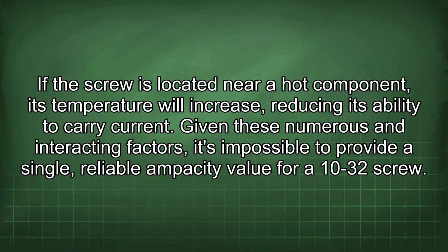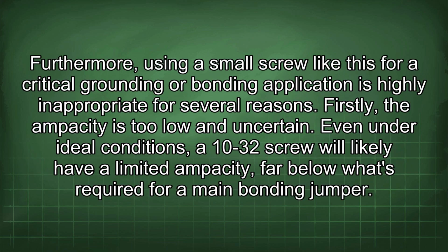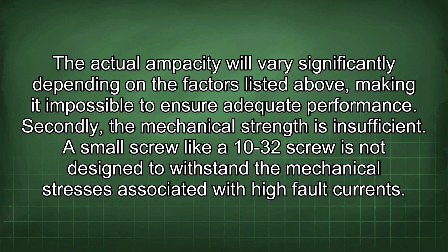Given these numerous and interacting factors, it's impossible to provide a single, reliable ampacity value for a 10-32 screw. Furthermore, using a small screw like this for a critical grounding or bonding application is highly inappropriate for several reasons. Firstly, the ampacity is too low and uncertain. Even under ideal conditions, a 10-32 screw will likely have a limited ampacity far below what's required for a main bonding jumper. The actual ampacity will vary significantly depending on the factors listed above, making it impossible to ensure adequate performance.